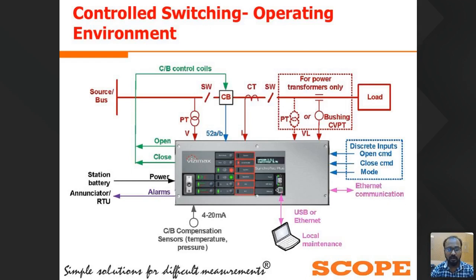After that, another important parameter is the circuit breaker compensation parameters. As we all know, the circuit breaker's mechanical operation depends on various parameters. For example, the breaker operating time depends on the coil voltage, circuit breaker mechanical pressure, the ambient temperature, as well as the SF6 gas pressure. So all these parameters will affect the breaker operating time. To calculate the exact breaker operating time as per the present condition, we are installing sensors on the breaker to measure all these parameters. So from these sensors, we can put the compensation.